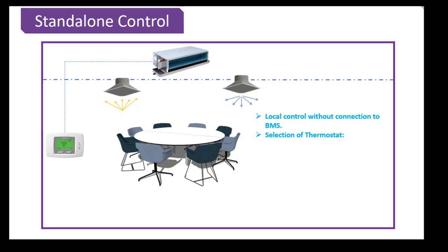Selection of the FCU thermostat for your application is very important. You shall keep the following things in your mind while selecting a thermostat for your FCU. First thing is the control voltage. Control voltage of the thermostat shall be matching with the requirement of an FCU. Second thing is your system two pipe or a four pipe system.